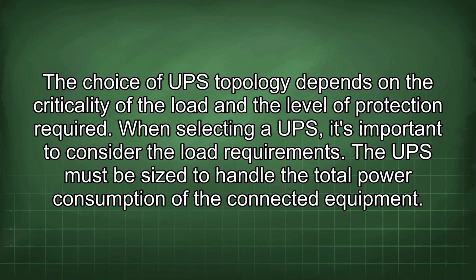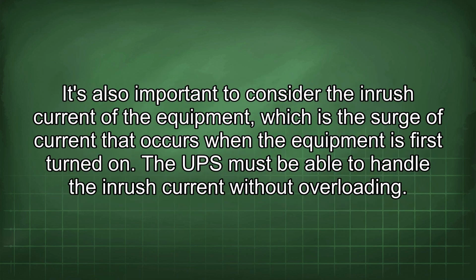When selecting a UPS, it's important to consider the load requirements. The UPS must be sized to handle the total power consumption of the connected equipment. It's also important to consider the inrush current of the equipment, which is the surge of current that occurs when the equipment is first turned on. The UPS must be able to handle the inrush current without overloading.